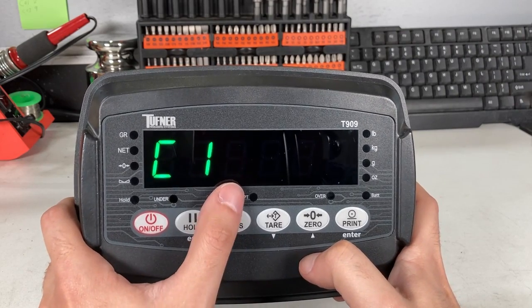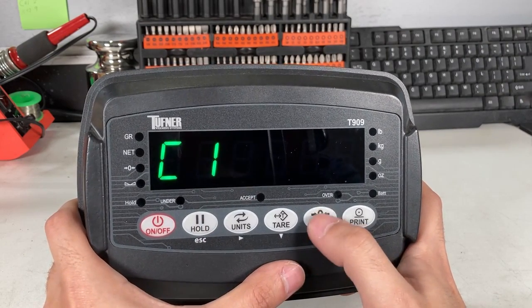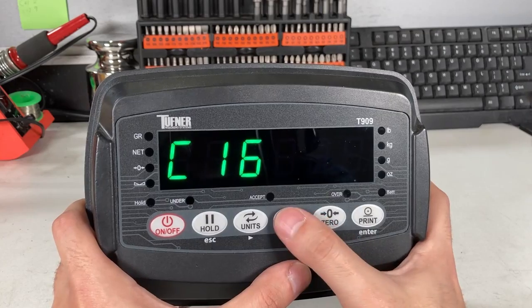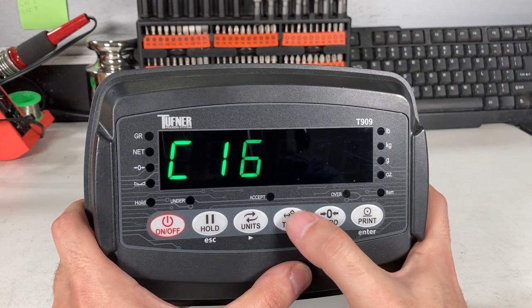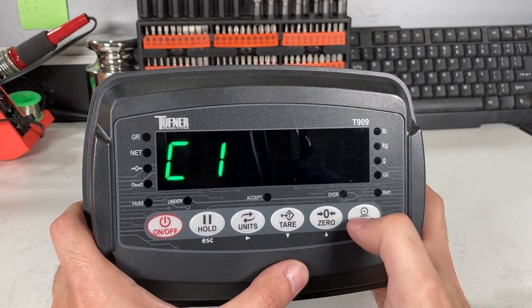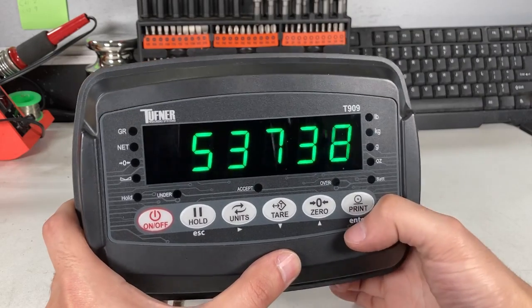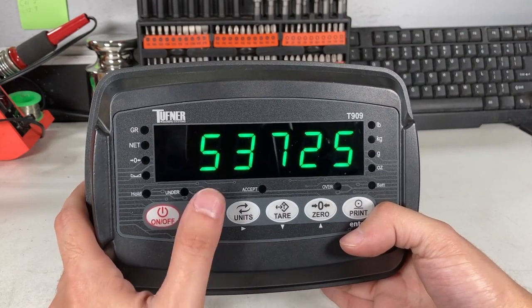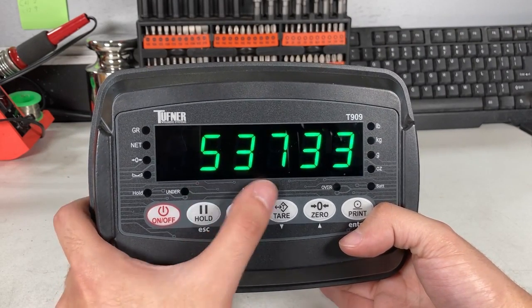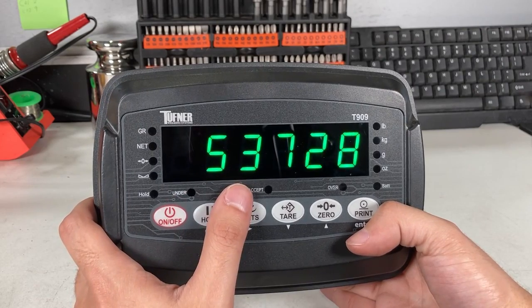Move right again to make the ones place flashing, and you press 0 to go to C16. I skipped over it, so I could go down, pressing enter. That's good, and now I can enter in. And you can see my raw data. This is what the calibration is based on. If you see all 9s, that means you connected something wrong.